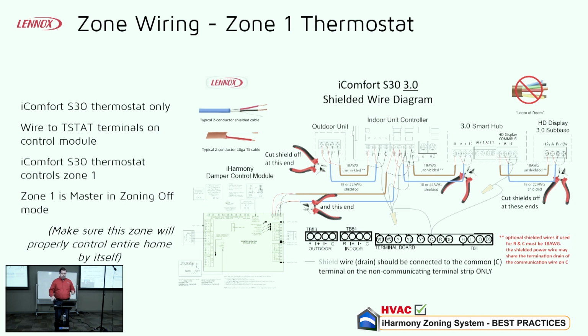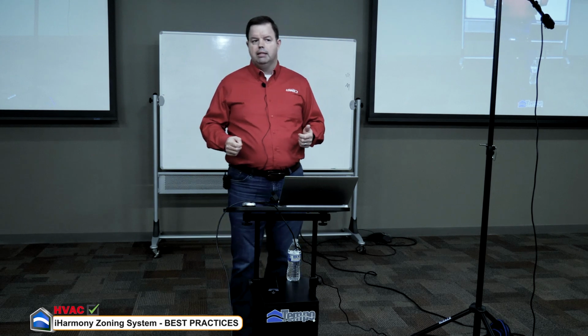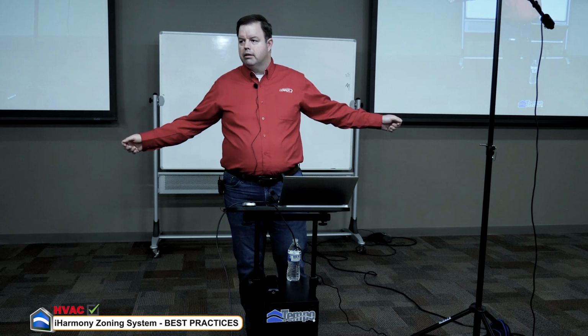problems, I'll say at very least, because usually you can reach out and touch the zone board and the smart hub from where the furnace or the air handler is, or it's somewhere close by. I'll say, hey, go to Home Depot, get you a run of 2 conductor wire, and have that in your back pocket, because there'll be a lot of situations where I'll say, take out that 8 wire, get just a basic run of 2 wire, run 1 for your R and C, run 1 for your I plus and I minus, and just getting those out from each other can prevent bleed over.